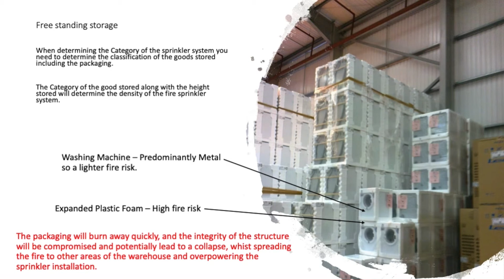So in an instance like this where you do have a fire, what's going to happen? What's going to catch fire is the plastic foam and the plastic wrapping. And that plastic wrapping and foam will burn away quickly. When it burns away quickly, the structure itself will lose its rigidity, and what could then happen is it could collapse. When it collapses, it's spreading the fire all over the factory floor and causing fires all over the place. That could overpower or overwhelm the sprinkler system. So in instances like that, I think that one's stored too high. It should only be 3 high and not 6. The sprinkler system's only set to a certain density to cope with that.